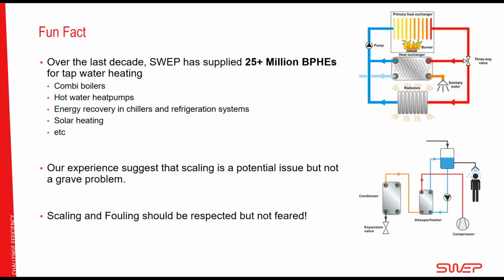Now we're in the fun facts. There's been so much talk about problems and fouling and scaling, etc. So I just thought, let's put in some real information here. Over the last decade, SWEP has supplied about 25 million brazed plates for tap water heating. Tap water heating, why do I mention that? Well, that's where we have tap water of different types of hardness all over the world, and so scaling is an issue. But we've been supplying to combi boilers, hot water heat pumps, energy recovery in chillers and refrigerator systems, solar heating, etc., that all were going towards sanitary water or shower water, right? This is a combi boiler, and this is a heat pump or an energy recovery module.